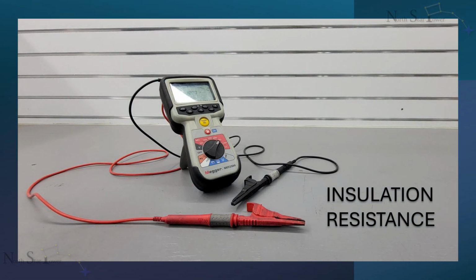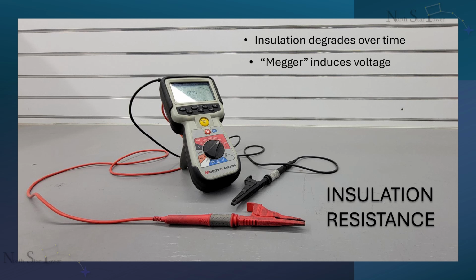The next test checks not where electricity should go, but where it shouldn't. Inside each breaker are insulating materials that prevent voltage from leaking to the frame, to nearby components, or to ground. But insulation degrades over time due to heat, moisture, dirt, and electrical stress. We use an insulation resistance tester, commonly called a Megger, to apply a high-voltage DC signal, often between 500 and 5,000 volts, depending on the equipment rating.